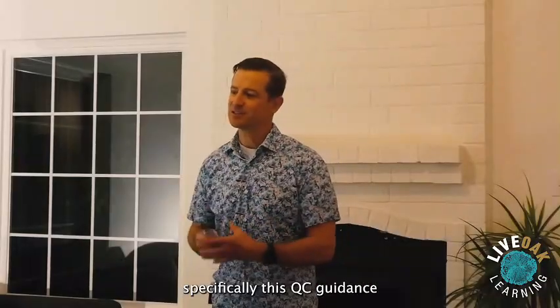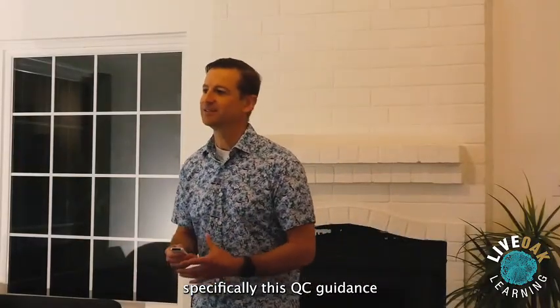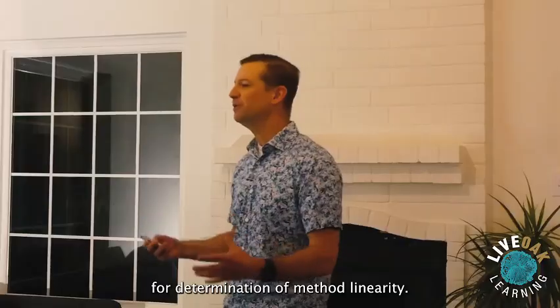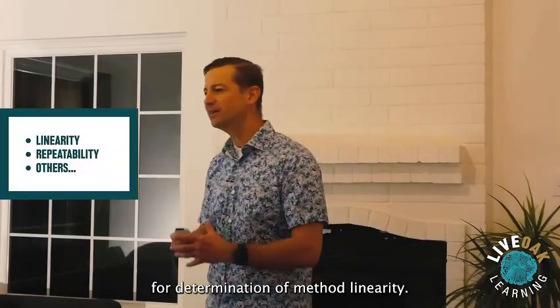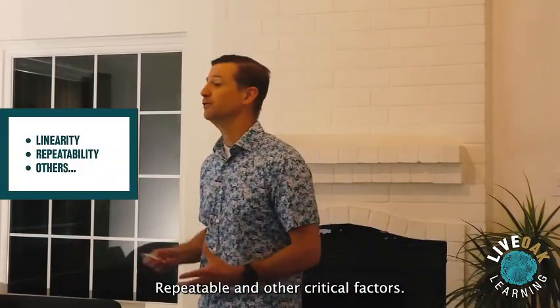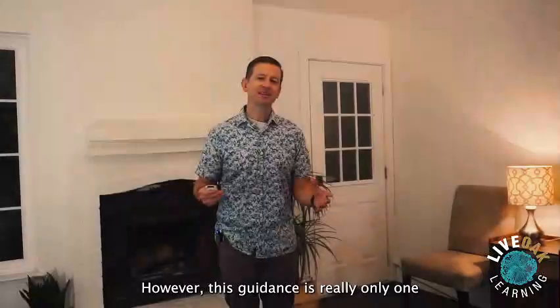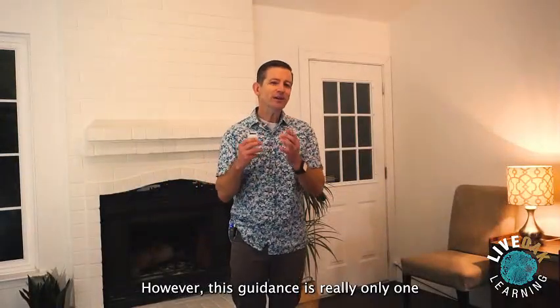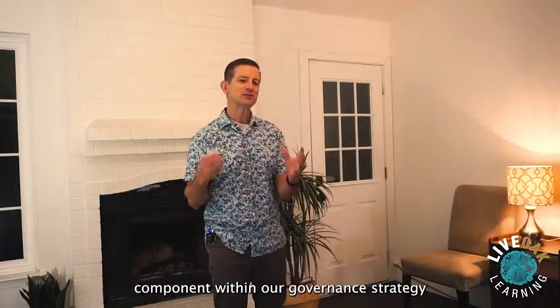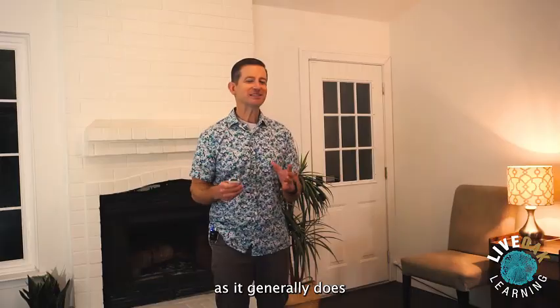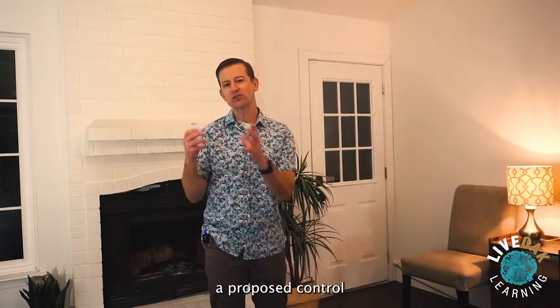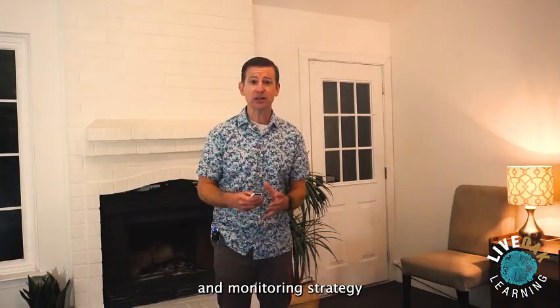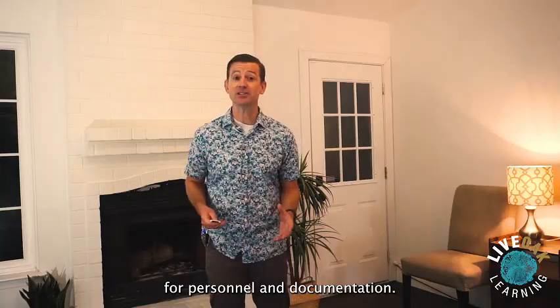This guidance, specifically this QC guidance, provides instructions for determination of method linearity, repeatability, and other critical factors. However, this guidance is really only one component within our governance strategy, as it generally does not include a proposed control and monitoring strategy for personnel and documentation.